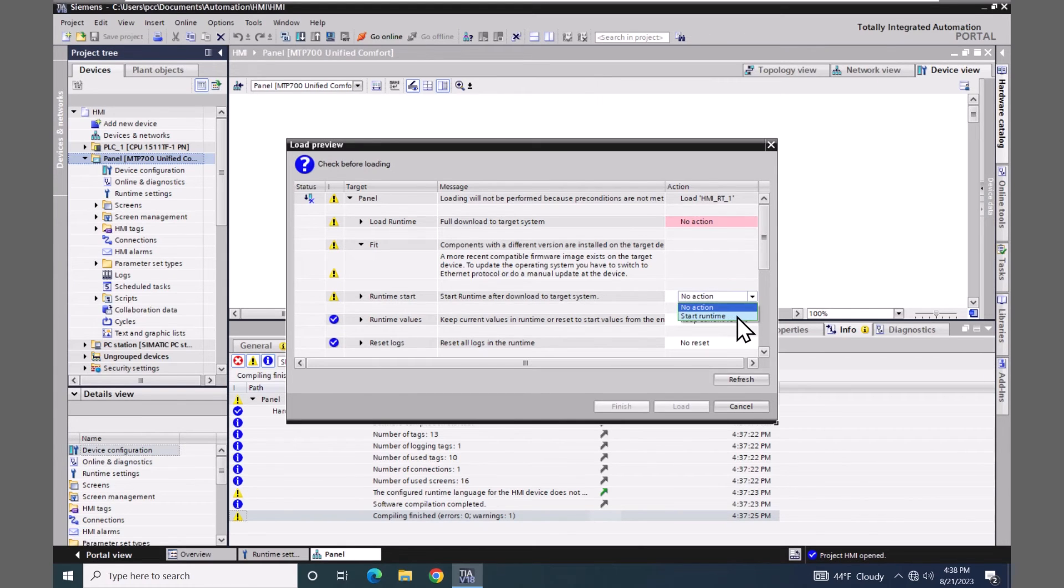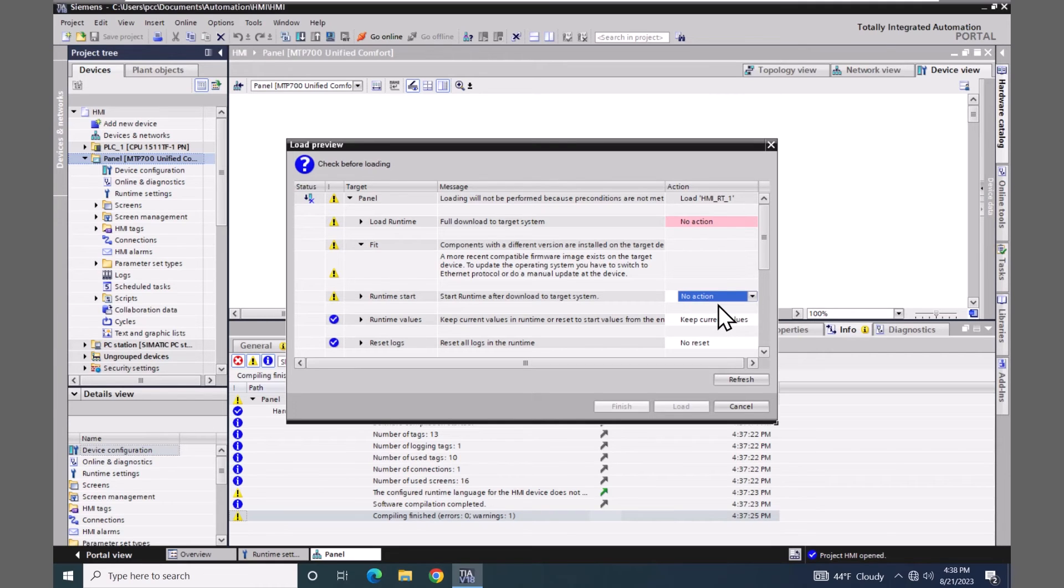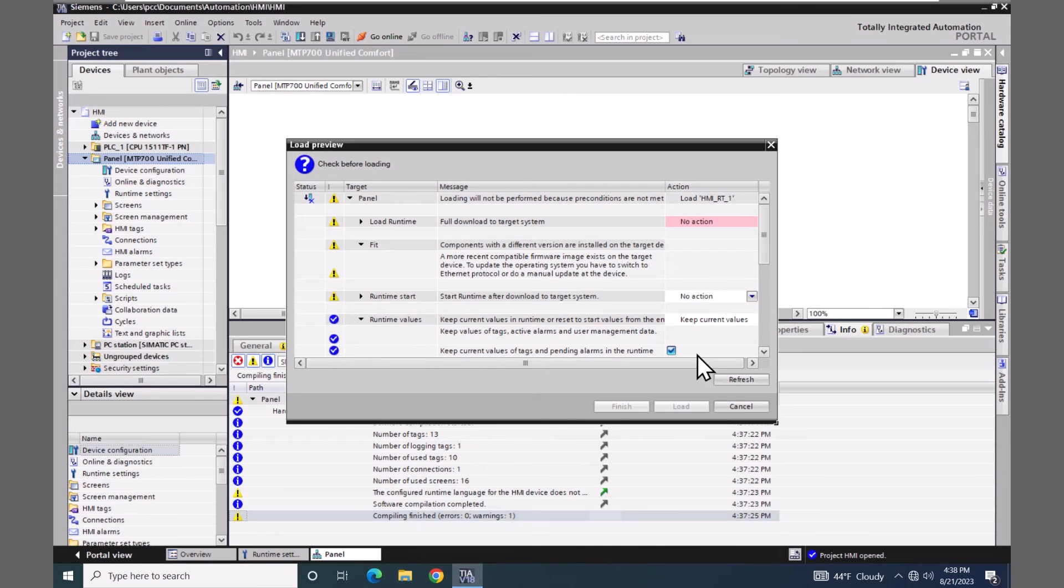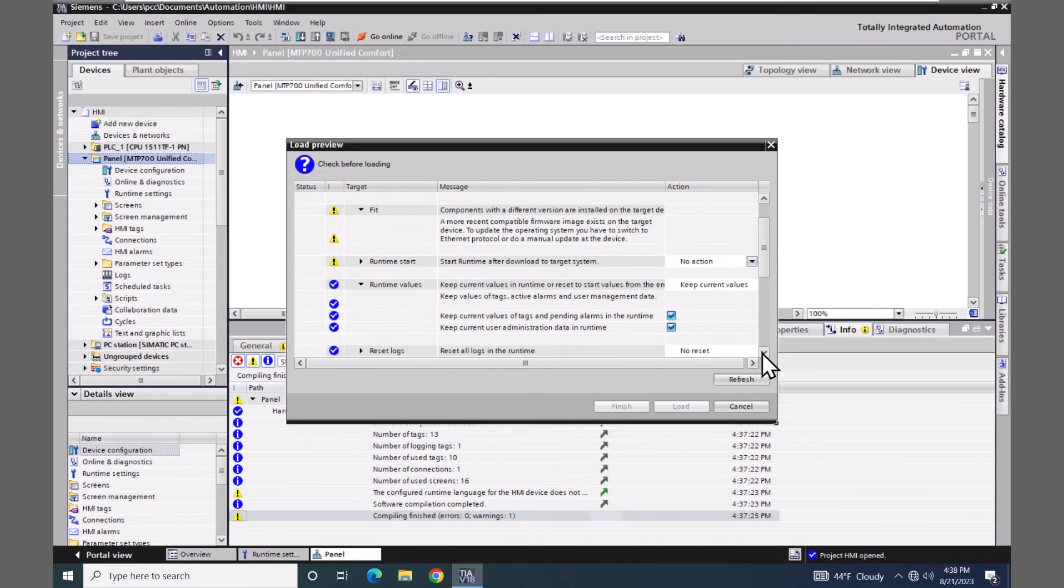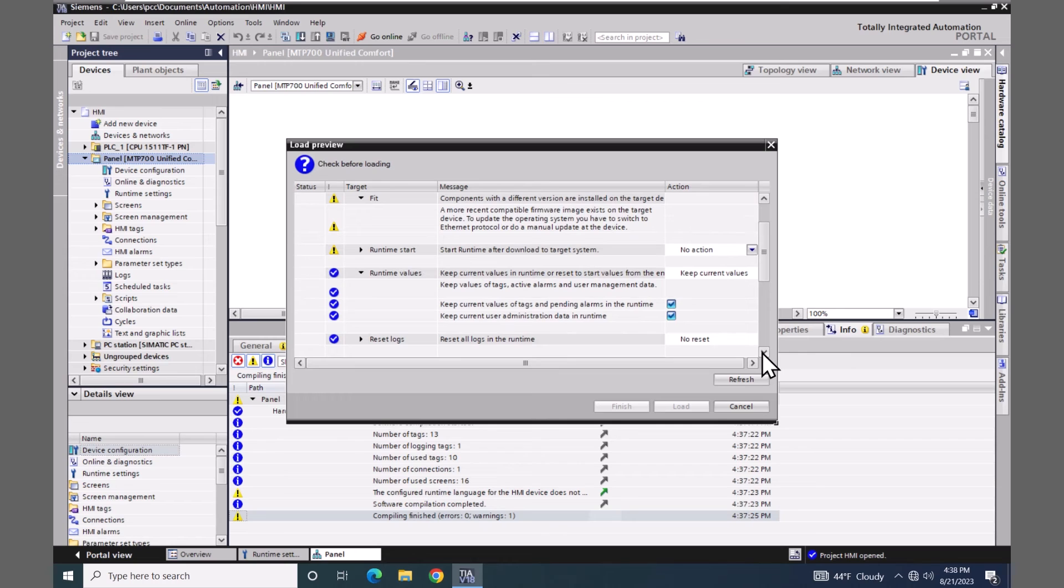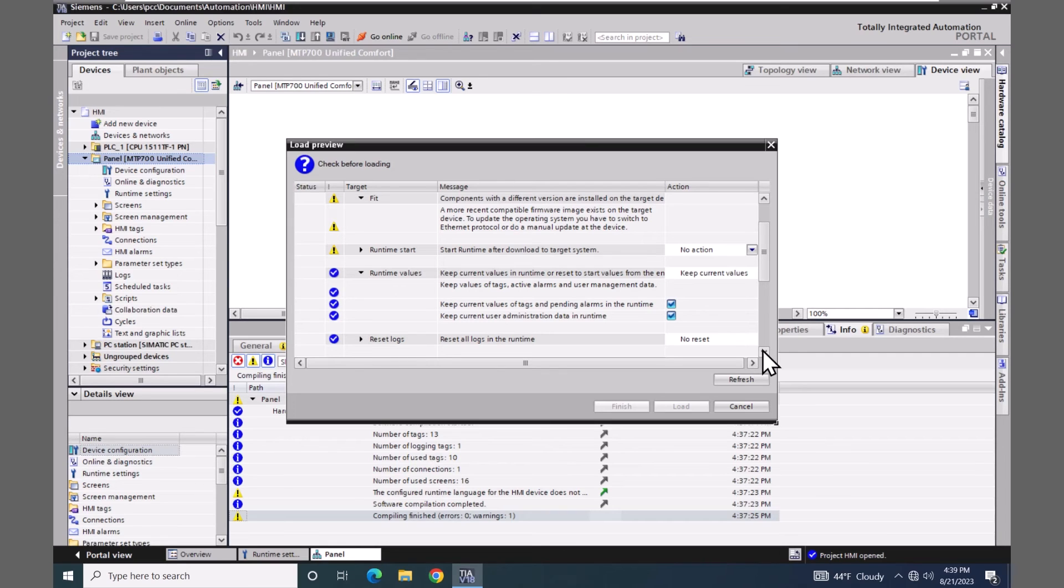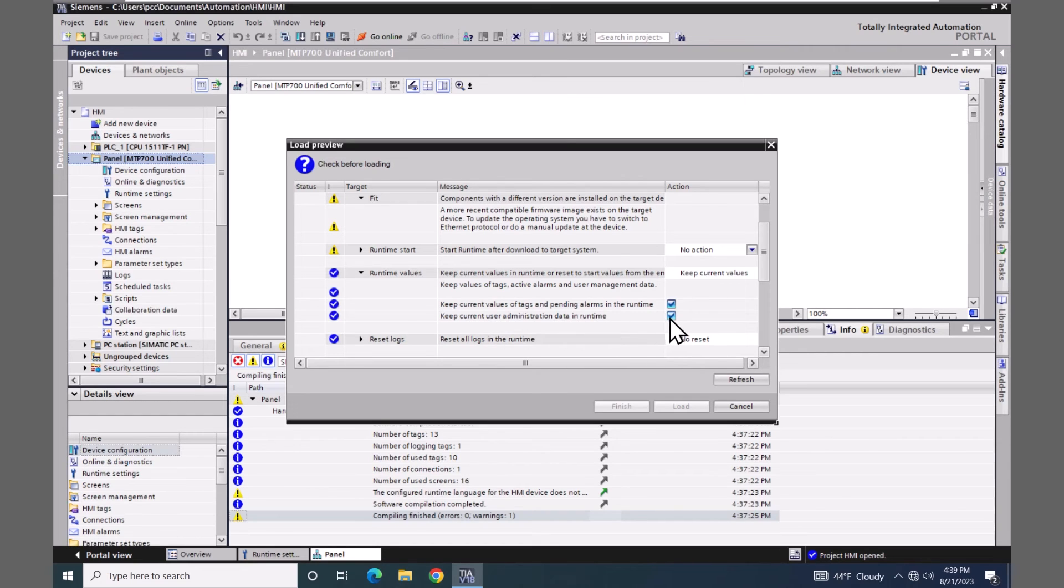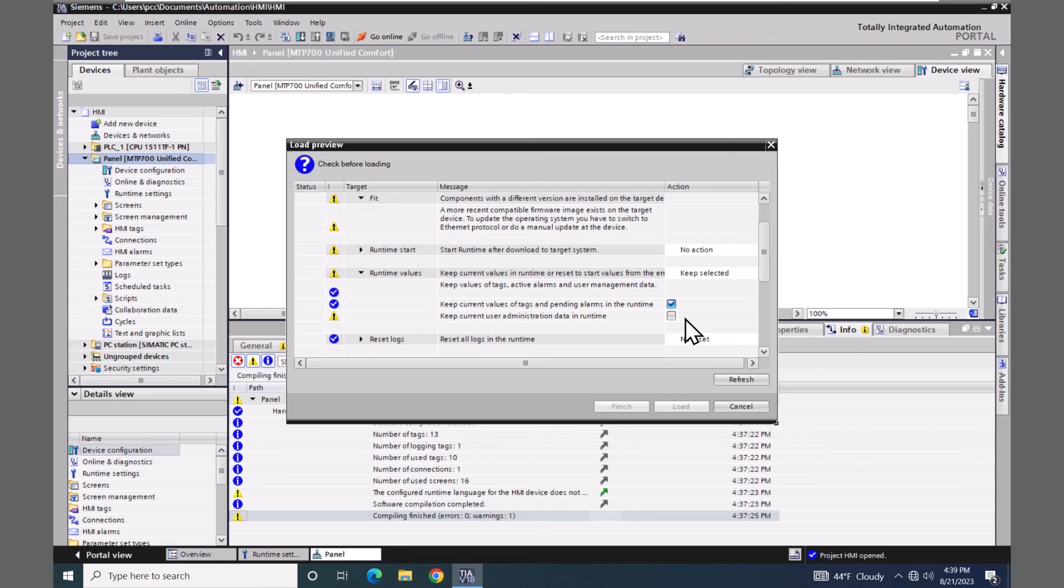For the runtime start here, if I select no action I do have a choice between no action or start the runtime after the download. I'll just keep it as no action. The runtime values - I will expand this out. When I look at the runtime values you have an option to keep the current values of tags or pending alarms in the runtime system or have them be reset to their default values. There is this keep current user administration data in runtime. I am going to uncheck that, so that means that my user administration from my TIA Portal project will be put down into the unified comfort panel.